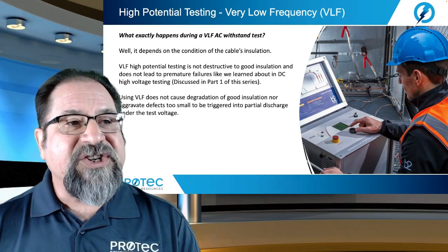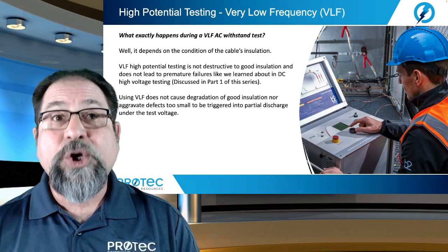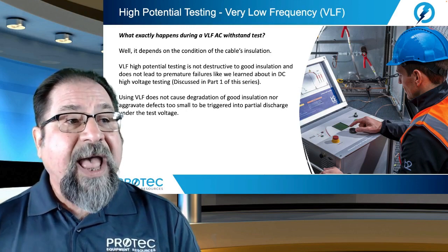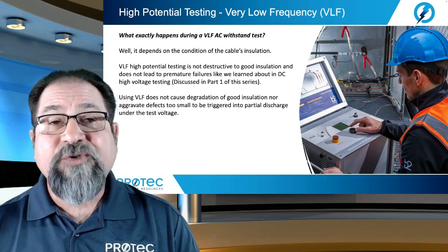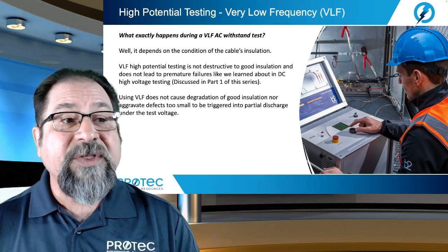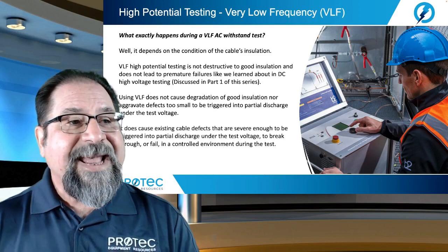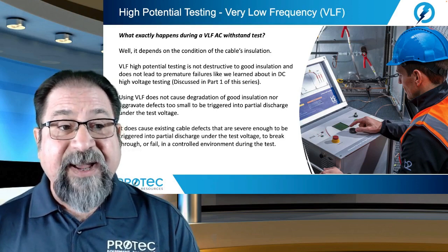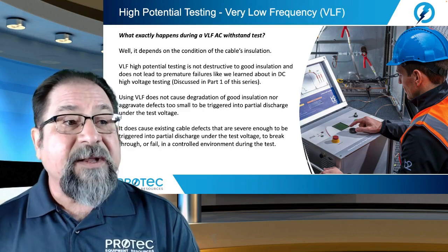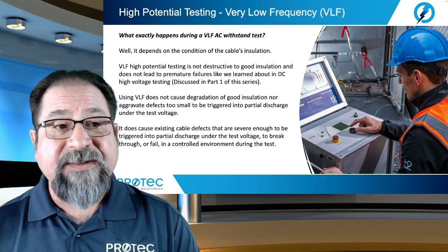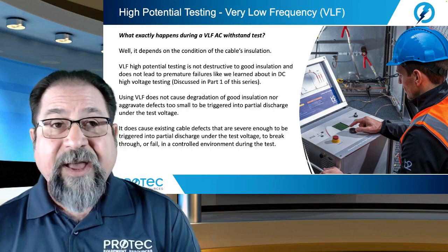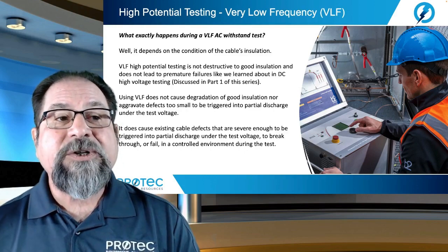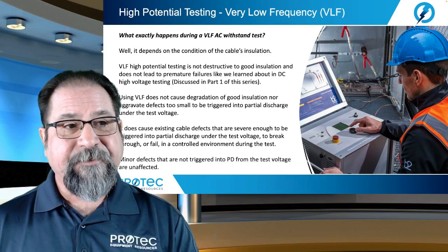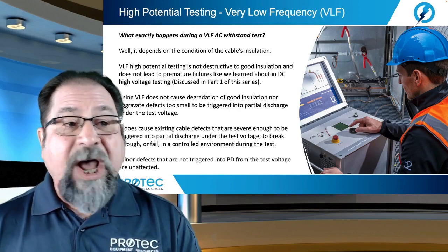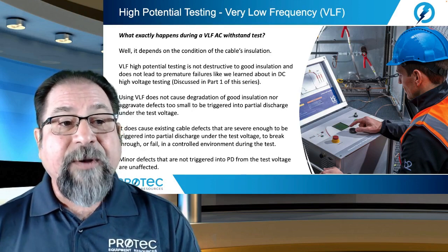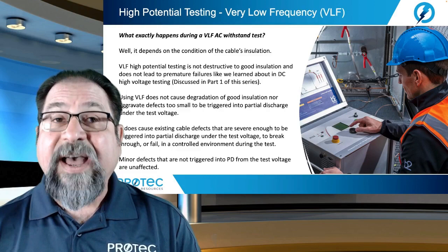Now, using VLF does not cause degradation of good insulation, nor aggravate defects too small to be triggered into partial discharge under the test voltage. It does cause existing cable defects that are severe enough to be triggered into partial discharge under the test voltage to break through or fail in a controlled environment during the test. Minor defects that are not triggered into partial discharge from the test voltage are unaffected.